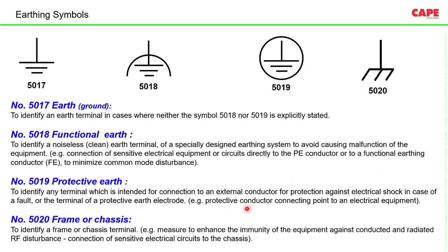So understanding the earthing requirement in a medical area is a little bit critical. It is a little bit technical as well. But you know what I am showing in the picture, 5017, 18, 19, and 20. These are called the earthing symbols, which are mentioned in the appliance. The appliance manufacturer should take care of his requirement, and appropriate marking must be made. The installer or the designer of that particular location has to understand the meaning and the method of making the earthing, and he should make it.